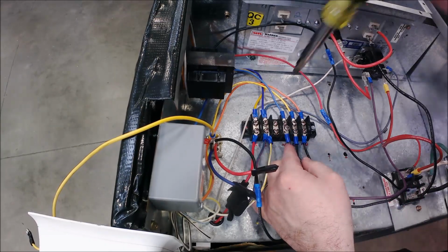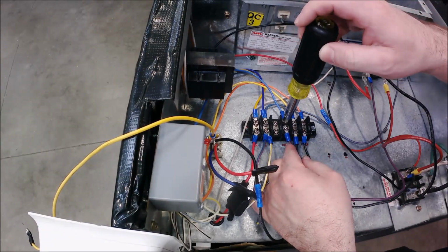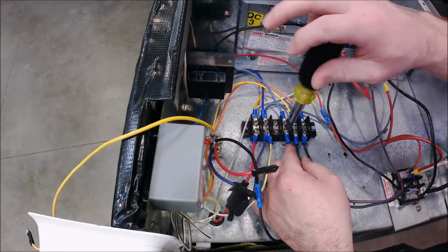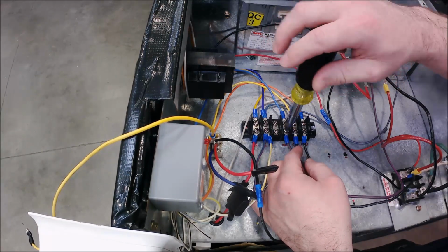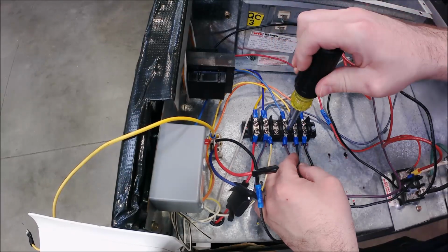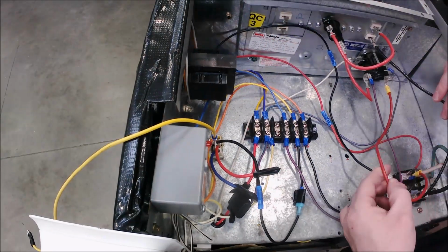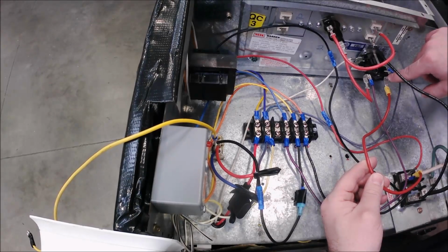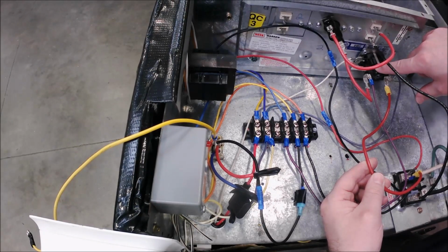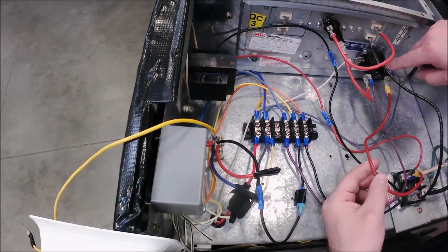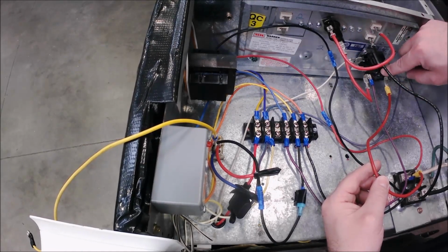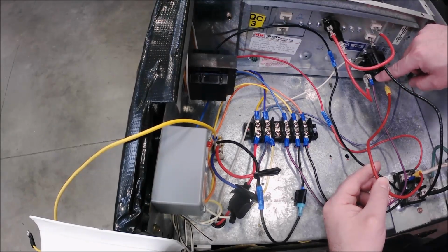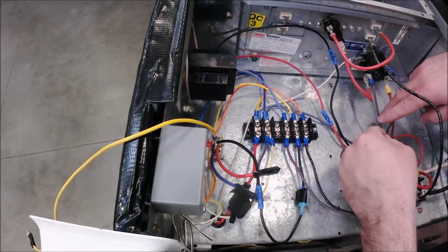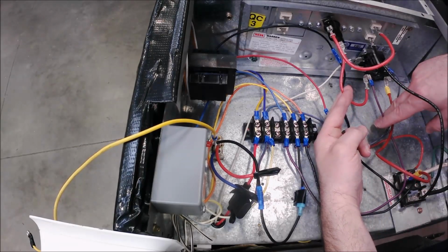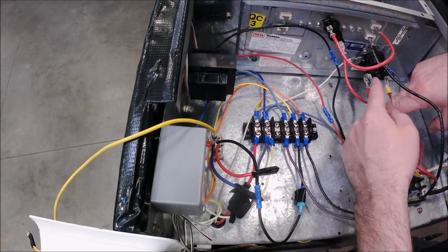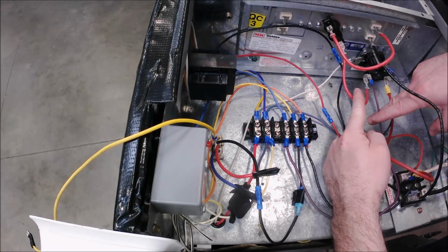I have this circuit right here, and it is a high voltage connection between the normally closed on the fan relay and the sequencer for the heat strip. Right here I've got L1 coming from the terminal block going into the sequencer. When the sequencer, on a call from W, that white circuit right there, is told to turn the heat on, that one wire goes through the switch, right? It brings power through the switch and it splits. One goes to the heat strip itself, and then we have this purple one. With the first heater that comes on, we need the fan to come on.